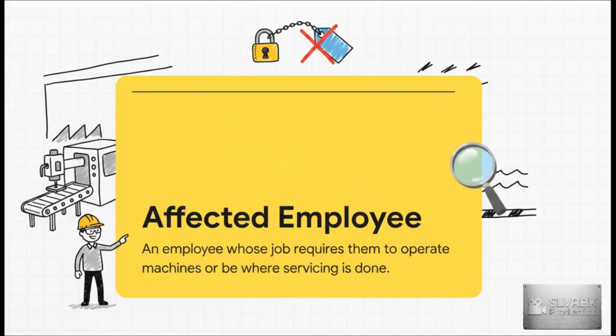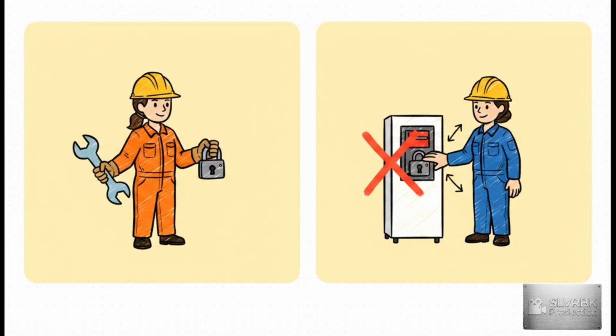Next, we've got the affected employee. This is usually your machine operator or user. Now, they don't perform the actual maintenance, and they aren't the ones doing the lockout/tagout activities themselves, but their job requires them to operate the machinery or just be in the area where the servicing is happening. So we're looking at 2 very different roles here, right? Which brilliantly illustrates their completely different training needs. Your authorized workers, the implementers, have a highly technical focus, recognizing and isolating those energy sources. Meanwhile, your affected workers, the operators, have more of a behavioral and conceptual focus. They must understand the fundamental purpose of LOTO. But most importantly, they need to recognize when a procedure is happening and know the absolute, non-negotiable rule of never tampering with lockout devices and never trying to start up locked-out equipment.